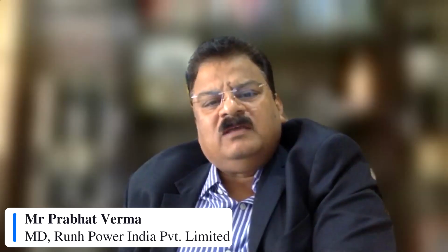Definitely, obviously, it will have impact on the heat rate, because sudden load increase and load drop is not the optimum way to run the plant. He has mentioned 50 times a day, it's too high, but definitely it will have impact on the heat rate and on the life of the components. But of course, whether 50 is too high depends on what the ramp up and ramp down is. If it is too high, that will have a significant impact on the life of the component.